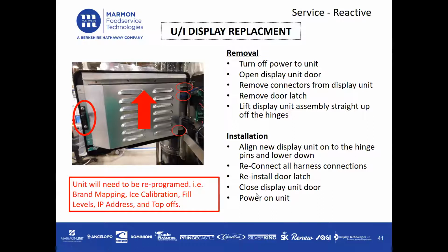There's a key note here: anytime you go through a UI display replacement, the unit will need to be reprogrammed. What do I mean by that? The brand mapping, ICE calibration, fill levels, IP address, and top-ups will need to be reprogrammed, because this display is what has all your settings programmed. So once again, if you replace a UI display, make sure you go back in and reprogram everything through the unit setup.